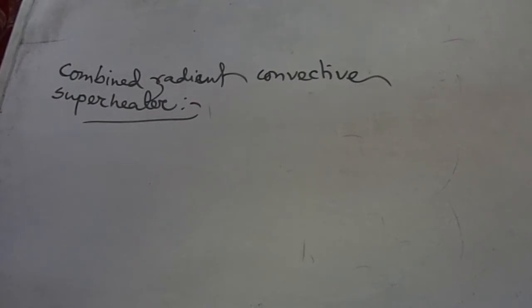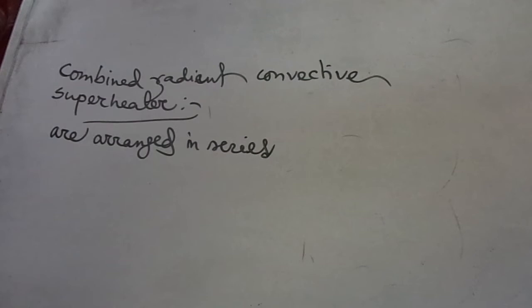Radiant and convective superheaters are arranged in series to yield relatively flat final steam temperature over a wide load range by taking advantage of their opposite steam temperature responses to load variation.